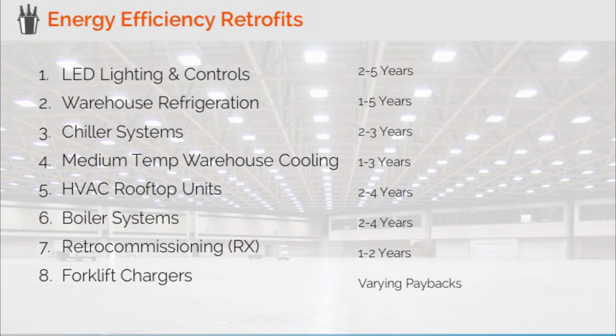Now, for those of you with boilers, adding an economizer will capture wasted hot flue gas and heat the feed water for the boiler. These are quick return projects and can be complemented by lowering stack pressure, installing variable frequency drives, and making sure you have the proper insulation in place. You could expect paybacks of roughly 2 to 4 years on boiler retrofits.